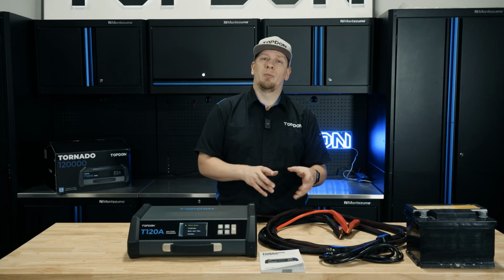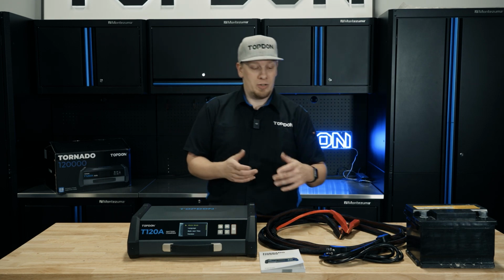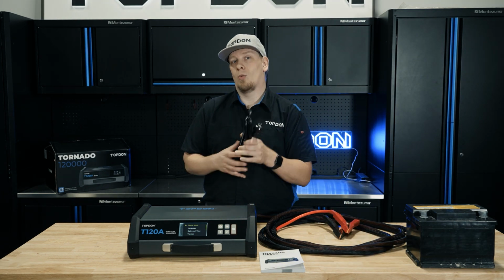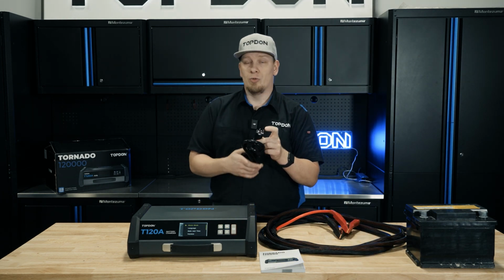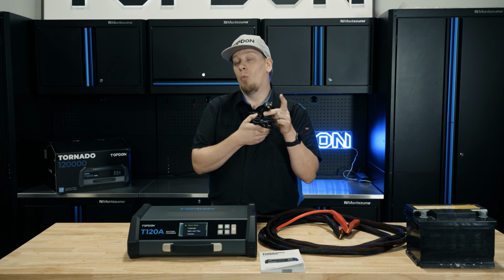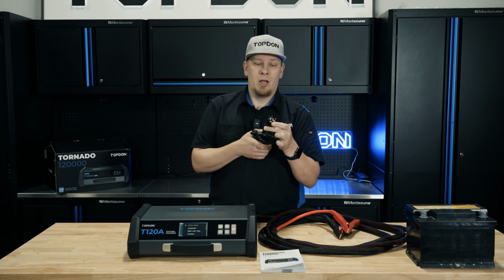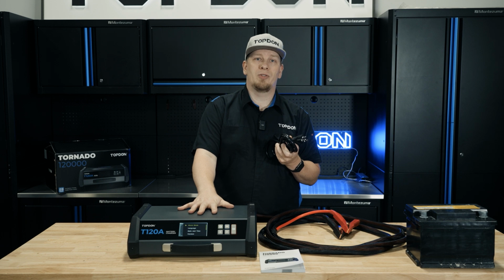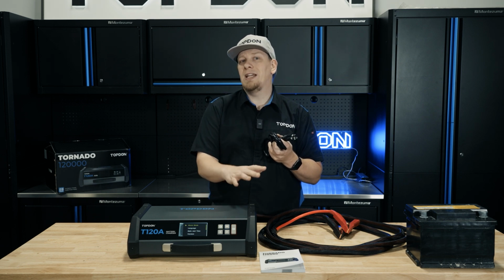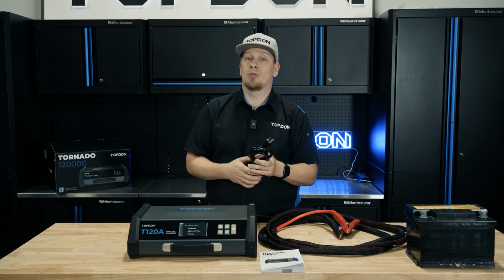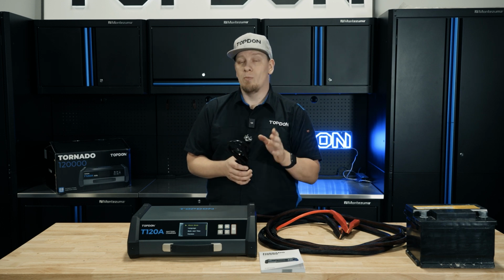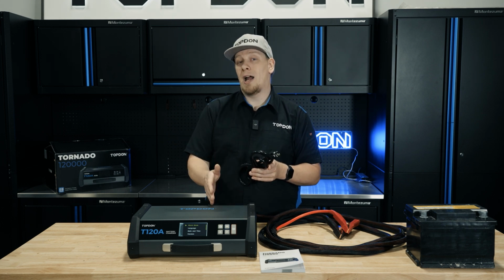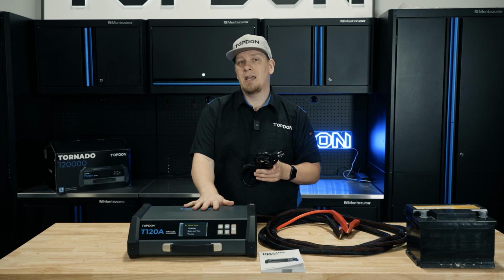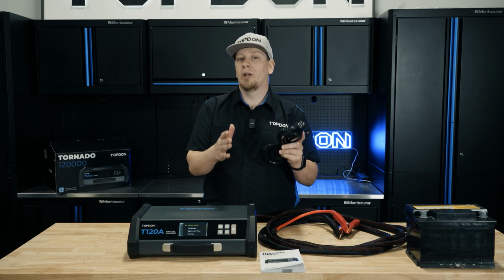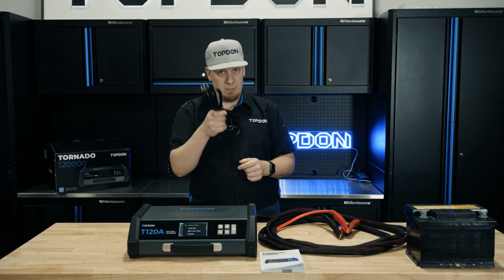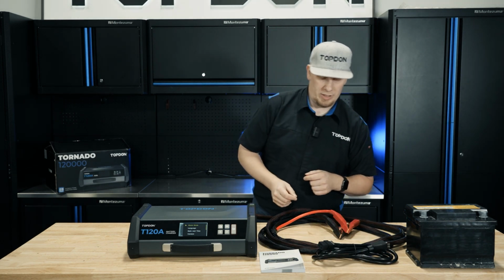We're going to show you a little bit of the hardware here. The unit comes with two cords for plugging into the wall for the US region. You have a 20 amp circuit, 110-120 volt. This is designed for when you're running higher currents to the T120A, so above 80 amps you should use this plug and make sure your breaker is a 20 amp. You may pop the breaker if you're running a higher current output and not using the appropriate cord, or at least a 20 amp breaker. So make sure to select the correct cord appropriately.